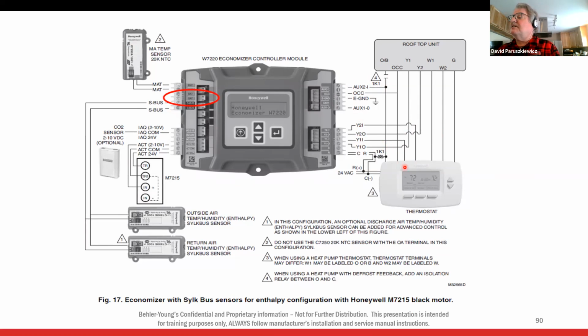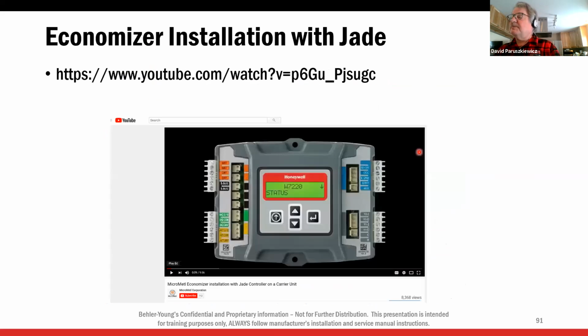where is it at? Yeah, our heating stage actually, oh, they don't show it here, but our heating stage actually, when we call for heat, we're actually going to send an output to the economizer module because these, remember the 2-stage blowers? So that we can bring on the second stage blower minimum position, and we'll talk about that in a second.